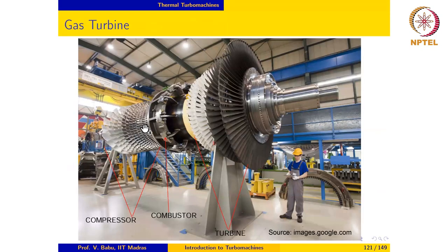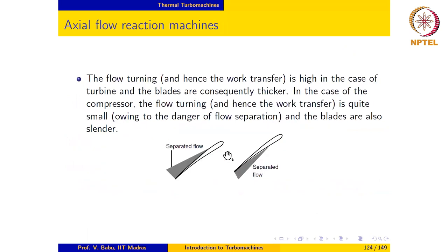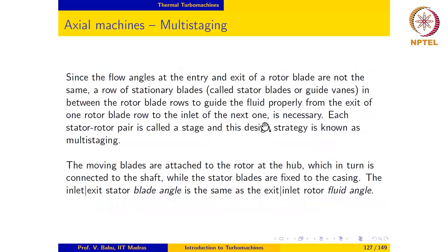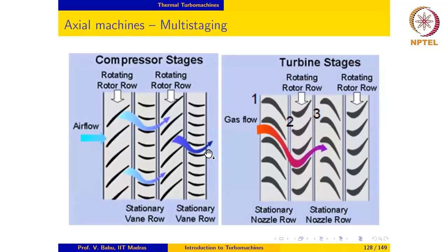The moving blades are attached to the hub, which is connected to the shaft. The stationary guide vanes are fixed between rotor blades and are attached to the casing. It is also possible to make the stator blades movable, in which case they are called variable guide vanes. The inlet-exit stator blade angle equals the exit-inlet rotor fluid angle.